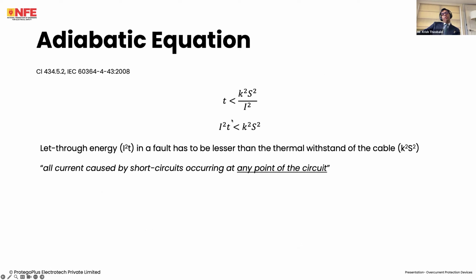When you have faults interrupted within less than 0.1 seconds, OCPD manufacturers will give you graphs quoting I squared T values. The electrical energy in a fault has to be less than the thermal withstand of the cable. And a cable will give a K squared S squared. Let me look at an example.